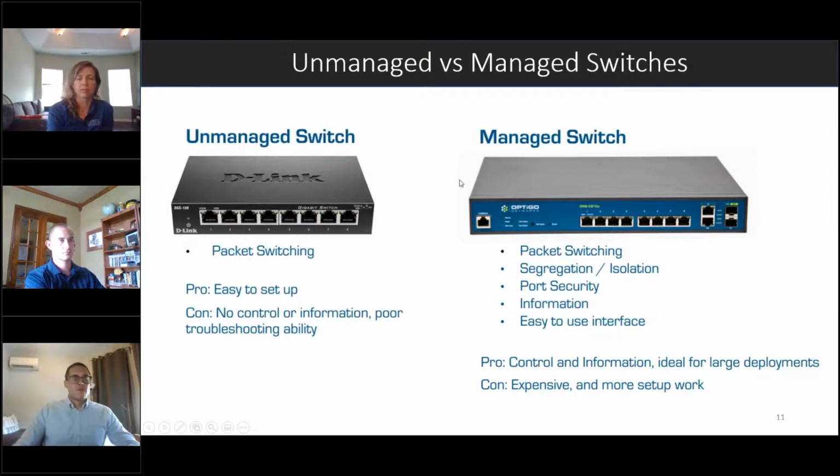Looking at network switches are also really important to the security of your system. So there are unmanaged switches, which have very little security features within them. And then there are managed switches. So you need to understand the difference between these two. On the managed switch side, you're able to set up those VLANs. You're able to provide the port security, lock out ports for people that shouldn't be accessing.